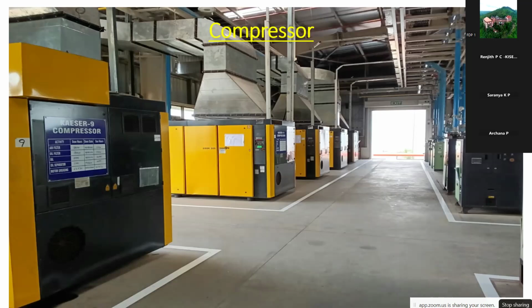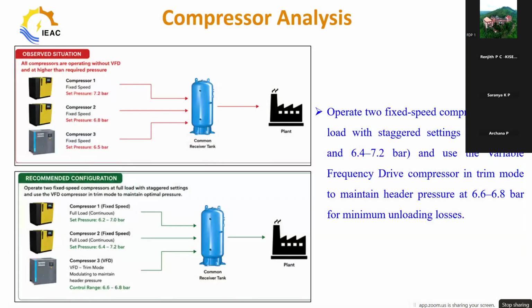Sometimes the compressor is operated at certain pressure settings. What is the required pressure for the equipment? If it requires 6 bar but they set the pressure at 8 bars, there is a large difference between the requirement and the setting. Matching the actual requirement with the pressure setting automatically saves energy. The loading and unloading time is also very important for compressor energy consumption and has to be analyzed correctly.